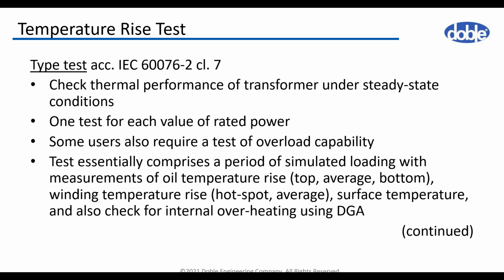If the transformer has more than one value of the rated power, for example, more than one cooling mode, the temperature rise test should be performed for each rated power. If agreed, the temperature rise test could be guaranteed and performed for a specific load cycle operation or overloading condition. Details for these are listed in part 7 of IEC 76 part 2.